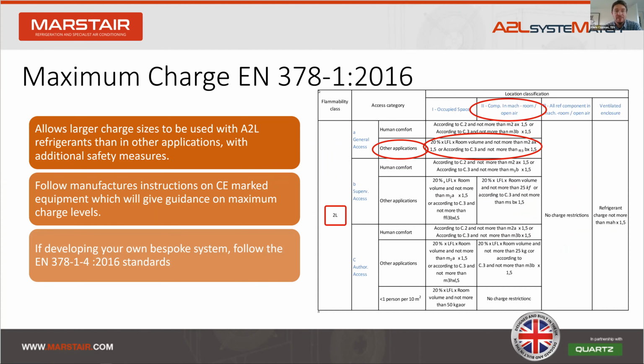So now we're going to have a quick look at EN 378. From a manufacturing point of view, this is what we've used as a standard, and specifically the table referring to refrigerant charge for A2L refrigerants. I'm now going to go through step by step how we've classified our equipment within the standard and what the refrigerant charge limits are for cold room equipment.